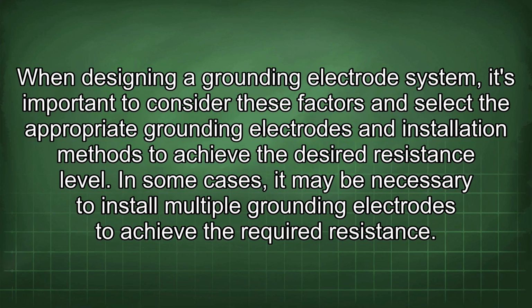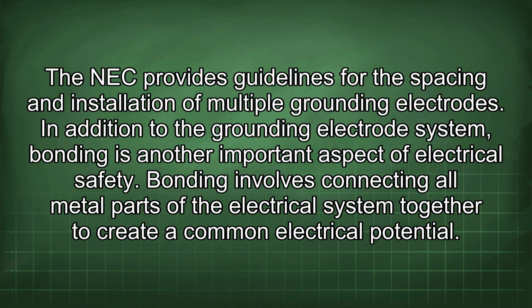When designing a grounding electrode system, it's important to consider these factors and select the appropriate grounding electrodes and installation methods to achieve the desired resistance level. In some cases, it may be necessary to install multiple grounding electrodes to achieve the required resistance. The NEC provides guidelines for the spacing and installation of multiple grounding electrodes.